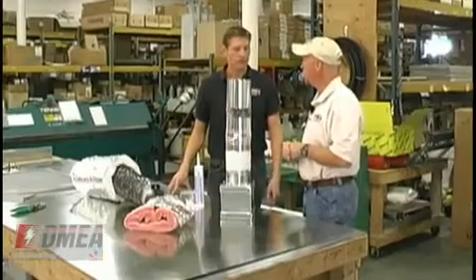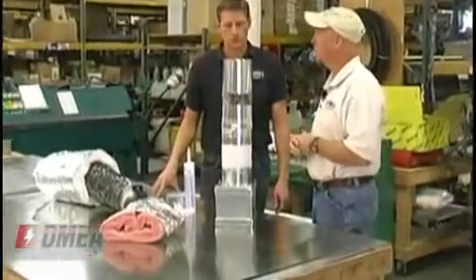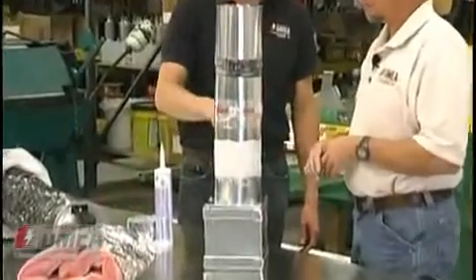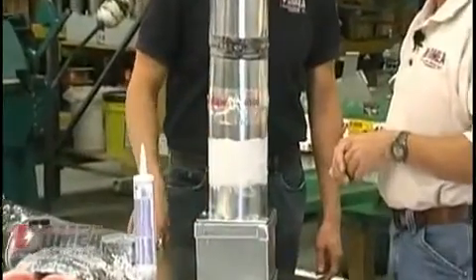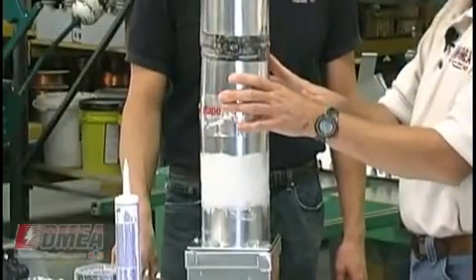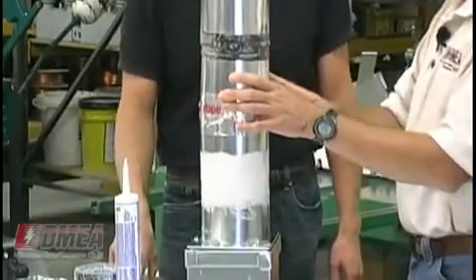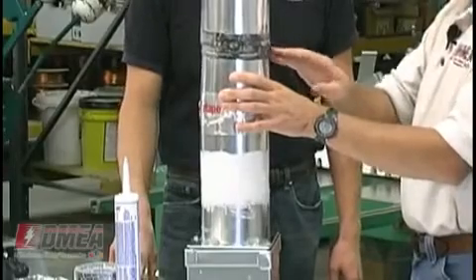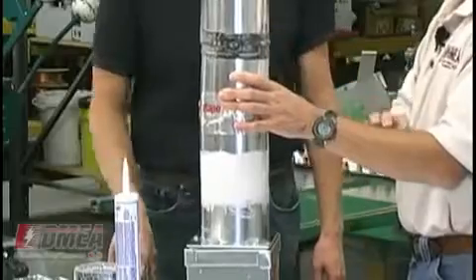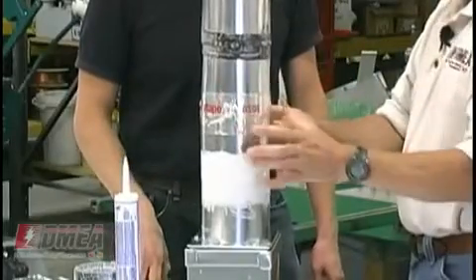So that could clearly be a significant savings. Yeah, you could save up to 20% on your heating bill just by taking care of your ductwork. So what do we have going on here? It looks like you've got a couple different types of sealants. Yeah, up here on the top, this was sealed with duct tape. Wow. Duct tape was never meant to be used on ducts. It actually will dry rot because of the heating and cooling going through this. So don't use that. This is metal tape.